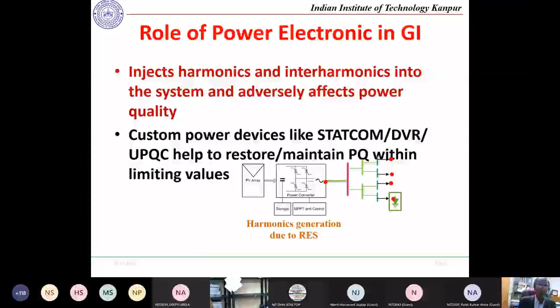Why is it a concern? We all know from our basic courses that it increases losses, increases noise, and causes torsional oscillation of the turbine-generator-motor-load pair set. In torsional oscillations, the generator shaft can be broken if a huge frequency component enters and excessive torque is generated in the turbine-generator system.